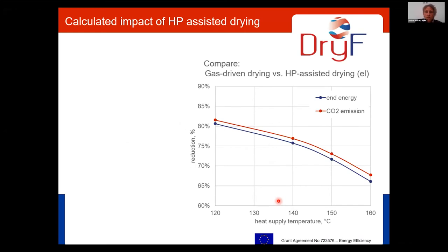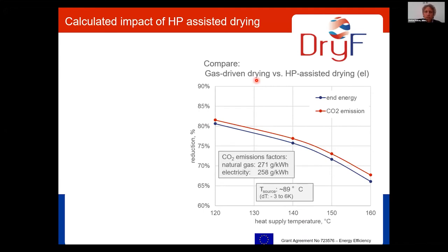When we look at the environmental impact, we see that the benefit drops the higher the sink temperatures are. But when you look at 120 degrees, where we operated in Uttendorf, calculations show that we can reduce energy consumption and CO2 emission by about 80% compared to a gas-driven drying process. The basis of these charts is that the energy source temperature was nearly 90 degrees. This was the absorption heat pump sink circuit. And the emission factors for natural gas and electricity are the Austrian values.